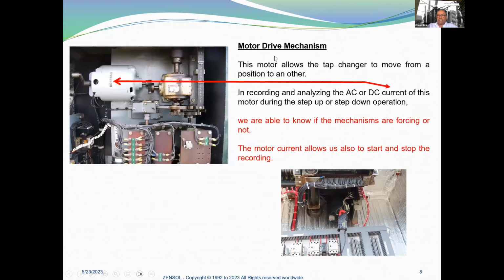The motor drive mechanism: this motor allows the tap changer to move from one position to another, and by recording and analyzing the AC or DC current of this motor during the step up or step down operation, we are able to know if the mechanism is forcing or not. Another piece of information is that the motor current also allows us to start and stop the recording. So in fact, we just focus on the window of the operation.